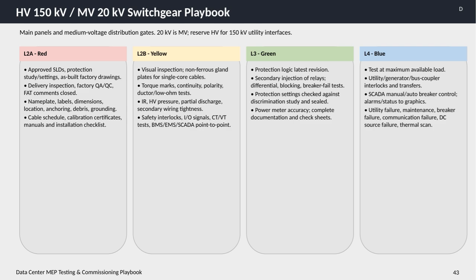It includes approved single-line diagrams, protection studies and settings, as-built factory drawings, and ensures that delivery inspections and factory quality assurance checks are complete. We also verify physical aspects like nameplates, labels, anchoring, grounding, and clear cable schedules, calibration certificates, manuals, and installation checklists. Moving to L2B, the yellow level.